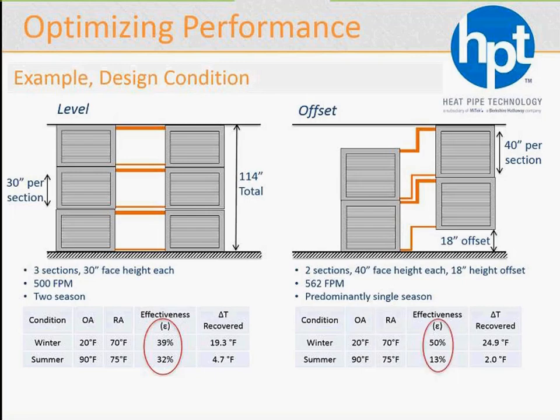How do we do effectiveness-wise? Winter, 50%, so 39 to 50%. Summer, because it's off-season, drops from 32 to 13%. But then again, most of your BTUs are in winter, and that's the premise for doing this product. So you're not being hit. It may sound or look like a fairly big summer loss, but if you don't have too many BTUs, you should not be concerned with that, and we'll show you that in the next example.